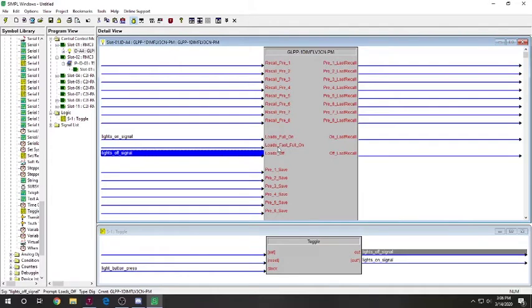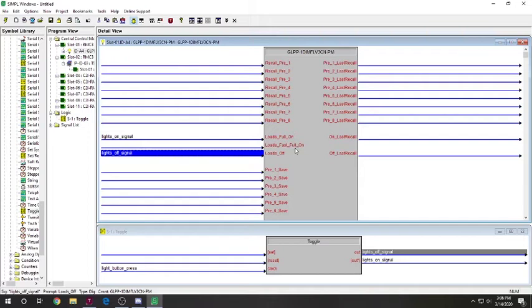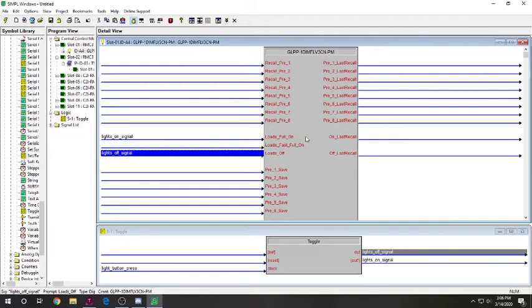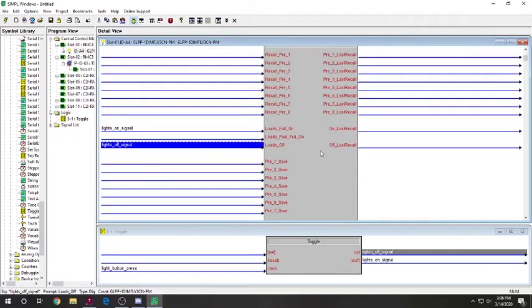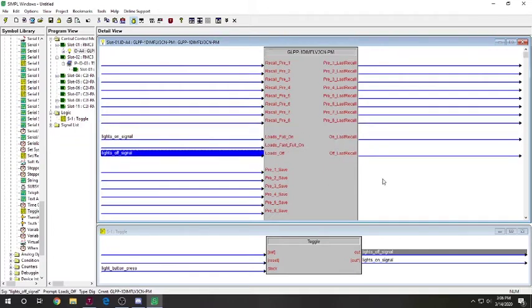So, we don't need this part anymore, the touch panel buttons. But we do still need the lights. So, let's shrink that down a bit and pull this down, make it nice and big. So, we are going to scroll down to right here. Loads full on and loads full off. So, we're going to drag the lights on signal to loads full on and the lights off signal to loads off. So, this is basically saying when the lights are on, turn them on. When the lights are supposed to be off, turn them off. Now, there's a difference between loads fast full and loads full. This loads full is going to make it a nice gentle increase and the loads fast full is just going to turn it right on. So, we're just going to be nice to everyone in the room and put it in the loads full on. Because, as you've probably experienced, jarring lights can be very distracting.